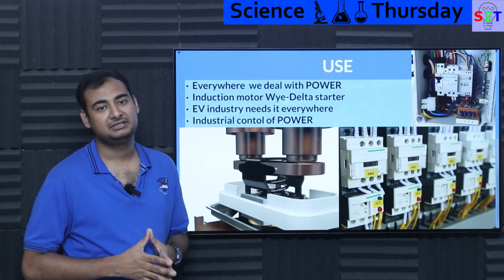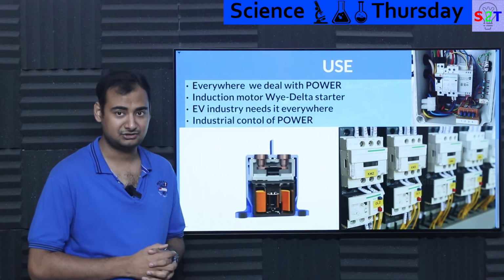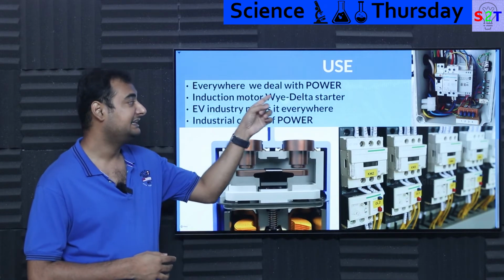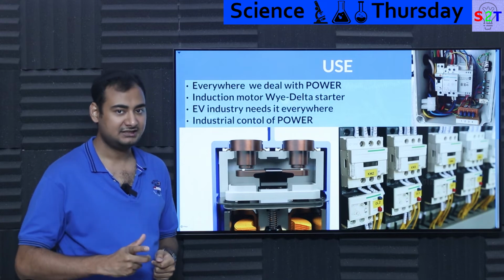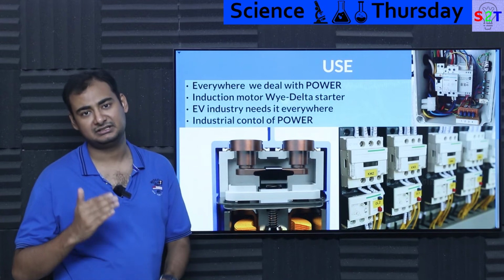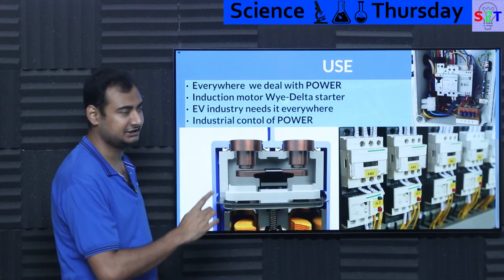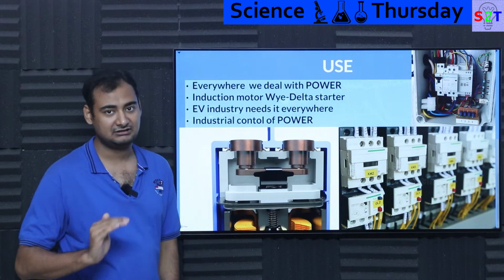Many times when dealing with a large power induction motor, people use what we call a Y-delta starter, meaning the motor starts spinning in Y configuration. It generally has much lower inrush compared to delta, though it still has some inrush.